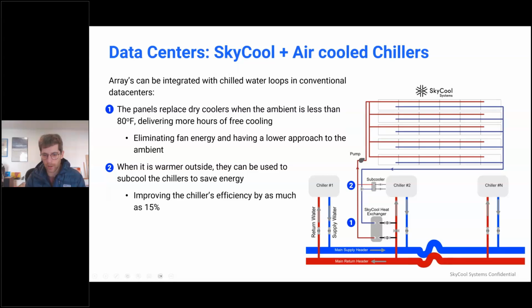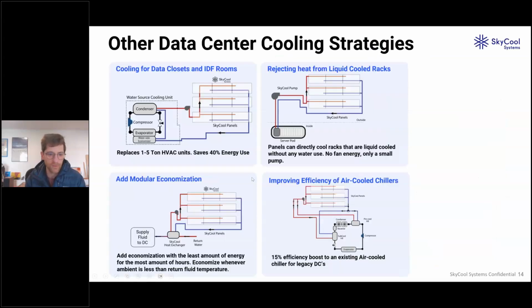So unlike dry coolers, which typically just sit idle during hot times, we can provide value to the chiller by subcooling it, and that adds efficiency, as much as 15% for the cooling cycle. So, cool. There are lots of different integration modes with data centers. Data centers are all somewhat unique. These are just a number of different designs that we've thought about.